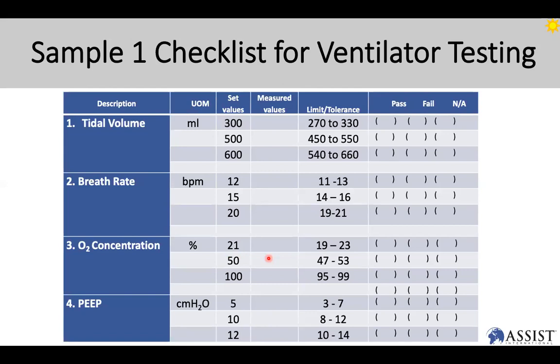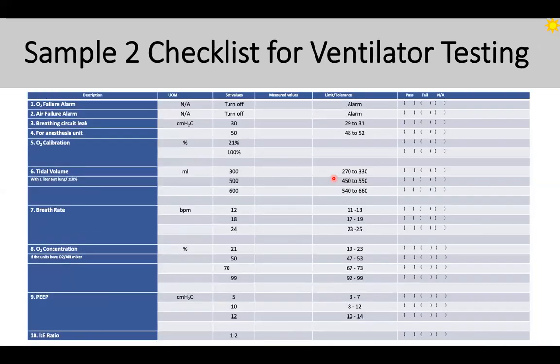For the ventilator itself, once you've attached everything as per the pictures we've shown, once you've connected it to the high flow modules, here are some of the parameters you're testing for: the tidal volume, the breath rate, the O2 concentration, and the PEEP values. You want to set it at a few different values and test the various limits. You want to record all of the measurements and ensure that it is within range.